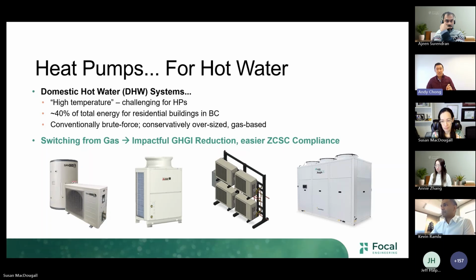And Hydro actually incentivized them, said you did the sizing, throw 2 more tanks on it, we just want to see what happens. So they intentionally oversized the storage volume, got an incentive from BC Hydro, and in exchange Hydro said in this trial we'd like the option to turn off your heat pump water heaters selectively when we're approaching peak load. Because we have this extra margin of stored hot water ready to go, no one's going to notice since it takes extra hours of demand to draw that hot water off, and meanwhile we can send that capacity to something more important instead of keeping these tanks warm when no one's taking a shower.